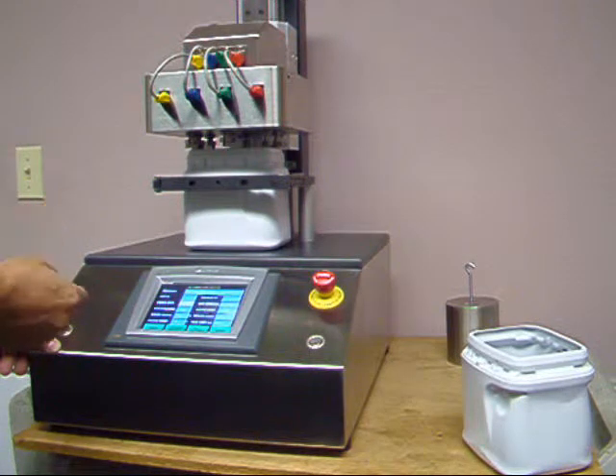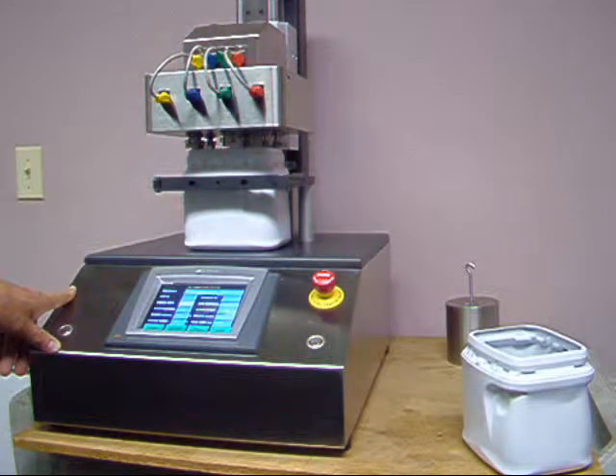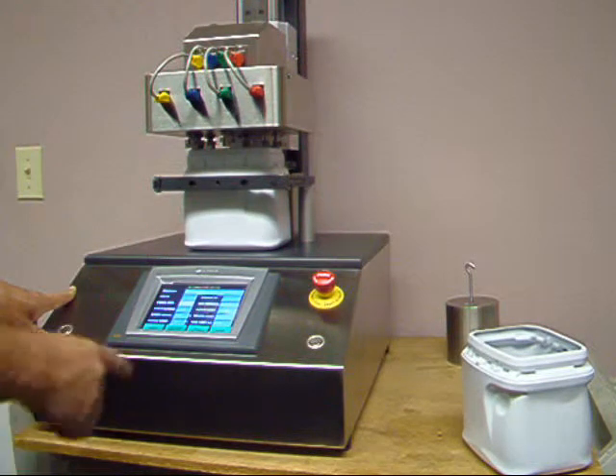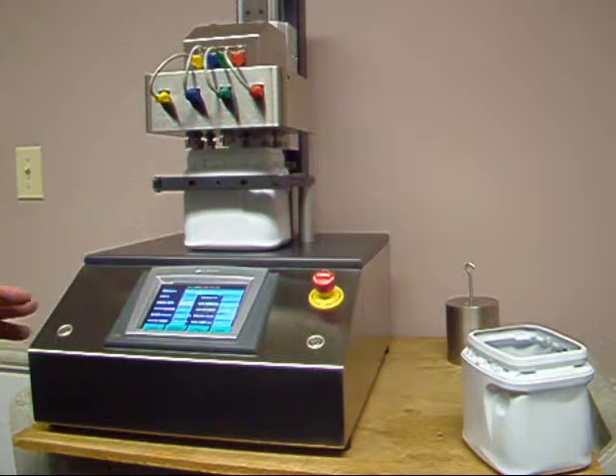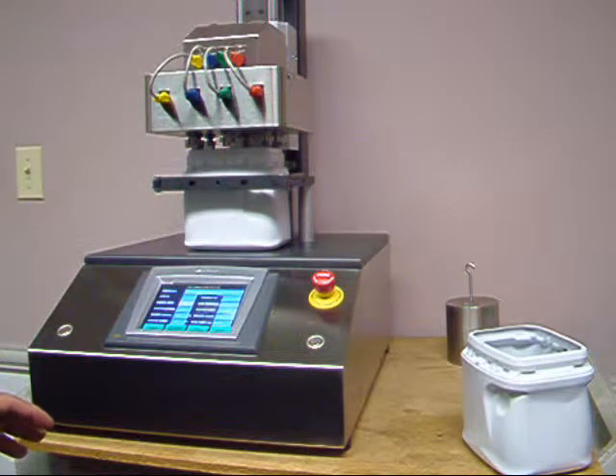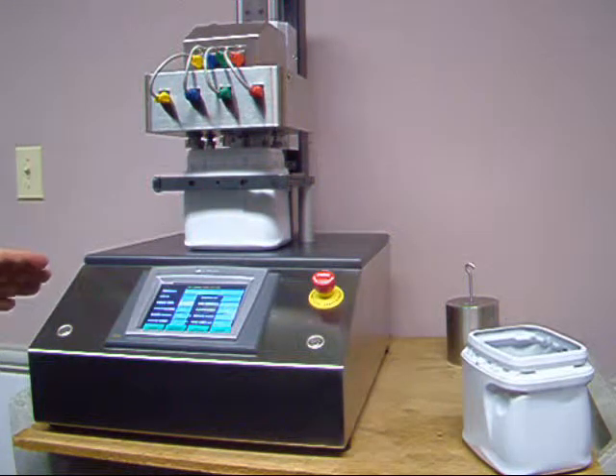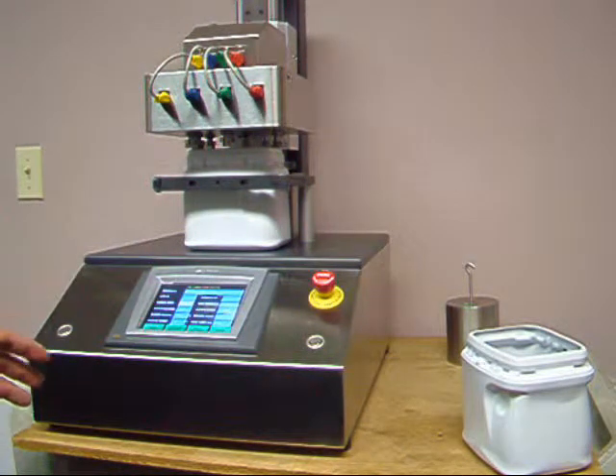If this will become an issue in the future, we can address it, but for now the unit is only measuring force in pounds. The speed can be adjusted between 0 and 20 inches per minute or even more, but I only tested it up to 10 inches per minute. The start force, I set it to 50%. This will tell the machine to immediately apply 50% of the motor's running torque when the test is started. So the motor will apply a constant 50% torque, and if that's not enough, you may have to increase that variable, but most of the time for the quarter-inch travel it will be fine.